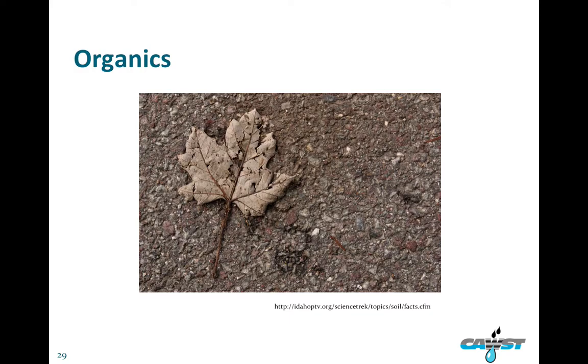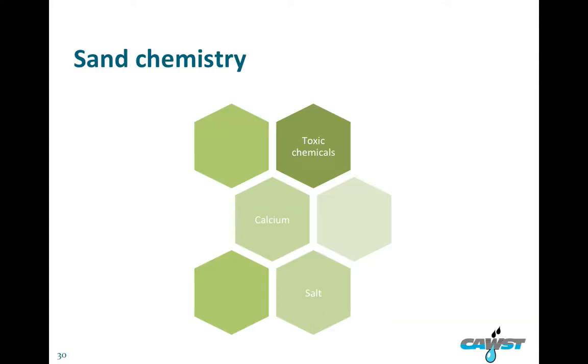Now, I was part of a project once that had this problem. It wasn't river sand in this case. We were using sand from a shallow pit, and since the pit was very shallow, there was probably organic contamination even though we couldn't see anything. We tried everything. We even bleached the sand and then thoroughly rinsed it. But after 1 year going back, the filters were still off. There were some other issues, but what it really came down to was that we should have used a different sand source.